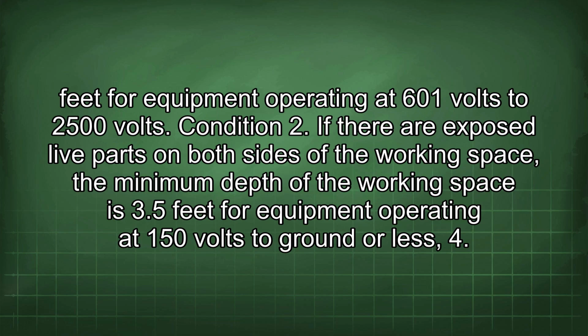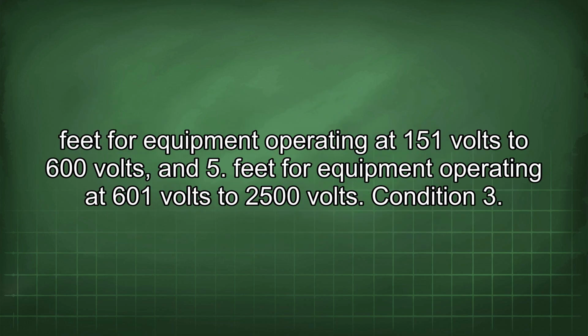Condition 2. If there are exposed live parts on both sides of the working space, the minimum depth of the working space is 3.5 feet for equipment operating at 150 volts to ground or less, 4 feet for equipment operating at 151 volts to 600 volts, and 5 feet for equipment operating at 601 volts to 2500 volts.